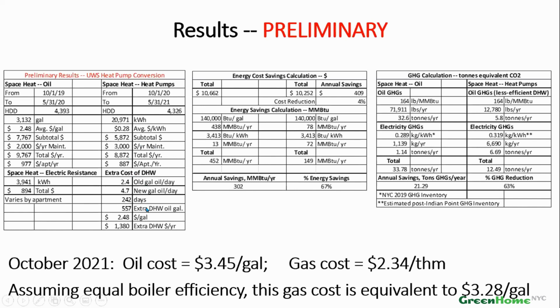There was one other cost which popped up recently that I hadn't expected. I should have thought about it in advance, but I didn't. When the system was using the boiler to make steam, it was using about 2.5 gallons of oil per day for domestic hot water. But now that it's not using steam, that almost doubled. So over the course of the heating season, based on the price of oil we had here, it was an extra almost $1,400 that, in my opinion, has to be included because it's an additional cost precipitated by the fact that they switched to heat pumps.